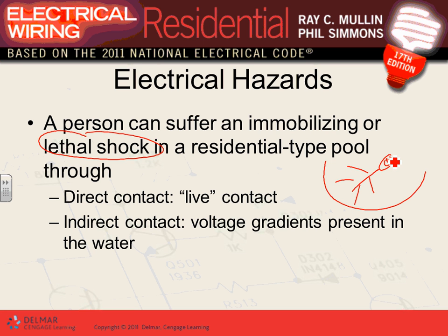When you're swimming in water, there are two types of shocks that you could be involved in. Direct shock: you're swimming and you grab an energized object. That's direct shock. And the other one is called voltage gradients. Probably you are not familiar with that. Everybody knows what a direct shock is, right? You grab an energized object while grounded, and you grab on the other side anything that's well grounded, like an object that's wet, and you're barefoot. How many of you swim with your shoes on? Nobody swims with their shoes on for the most part, right?